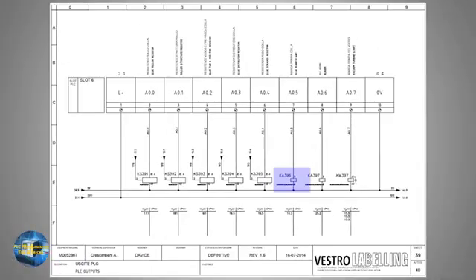This is the KA396 symbol for this relay coil. It looks like a rectangular box. You can see that one end of the coil is connected to the 0 volts line and the other end of the coil is connected to terminal number 7 of the PLC output card. Terminal number 7 is the A0.5 output of the PLC and it is mentioned here as glue pump start command.